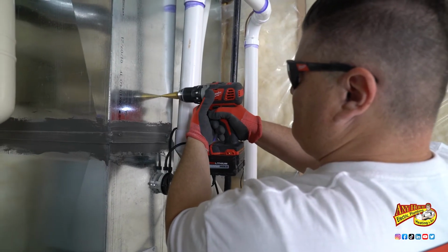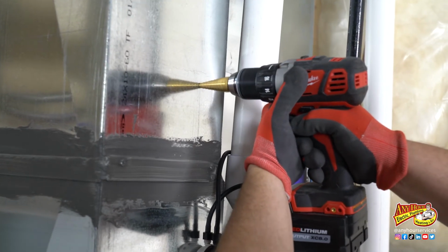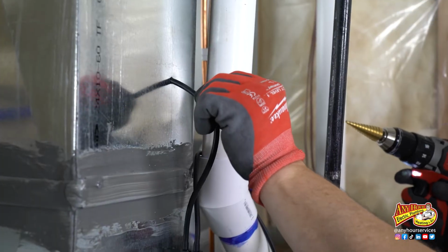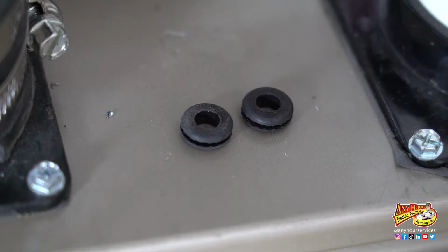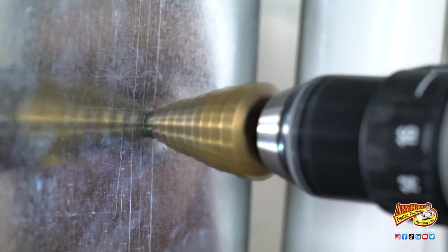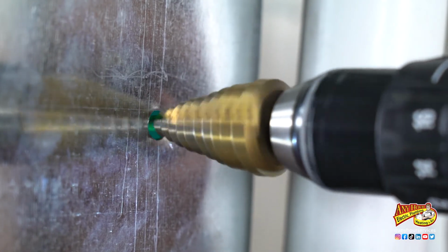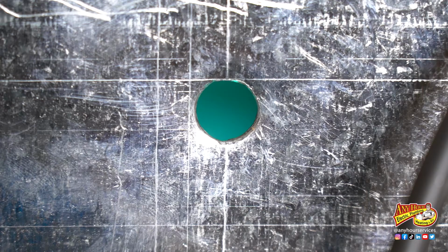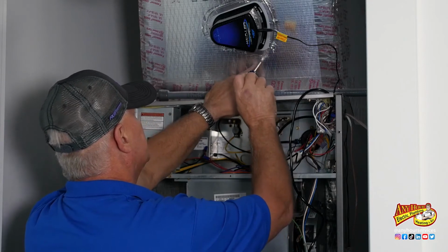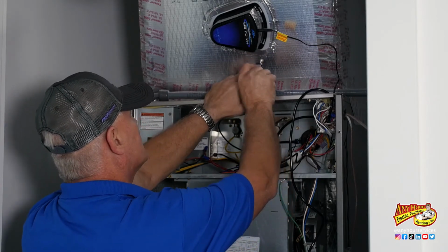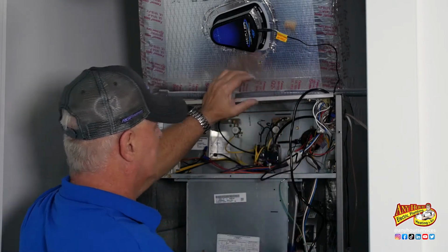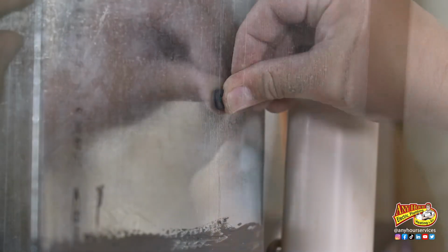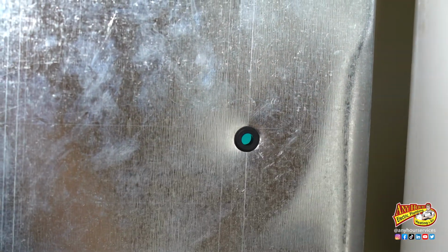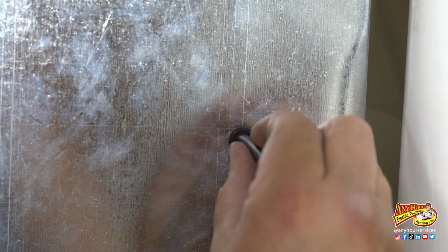Once you determine where each will go, mark and drill a hole larger than the tube, but not larger than the rubber grommets that were provided. If you're working with insulated ductboard, you can pop a screwdriver through and that should be pretty close to the right size. Thread about 2 or 3 inches of each tube through each grommet.